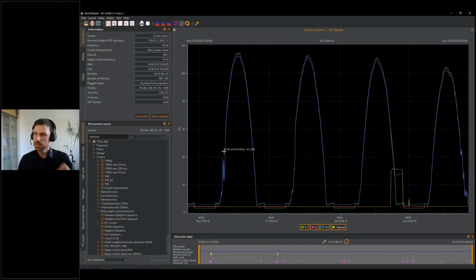So what I see is that the 10-minute average value, because the measuring interval is 600 seconds, which corresponds to 10 minutes, is around 112, 113 amps during the day. So we are at around noon in here, and overnight there is no current. So that's what I see in here. The recording lasted 4 days and 1 hour.